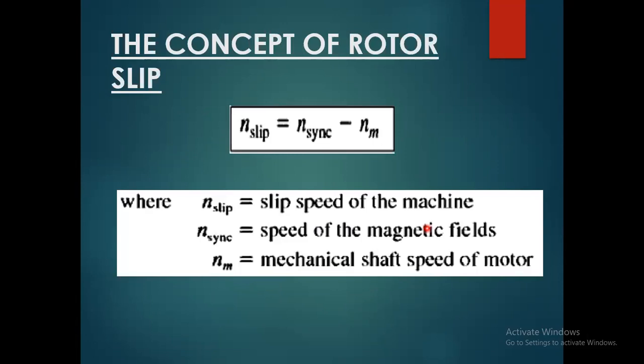Now, the concept of rotor slip. I already told you about slip in our previous session. Slip is the difference between the synchronous speed and the rotor speed. The main difference between these two speeds we call the slip, where n slip is called the slip speed of the machine, the synchronous speed is called the speed of the magnetic fields, and the mechanical shaft speed of the motor is represented by Nm.